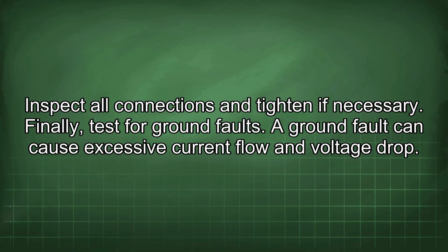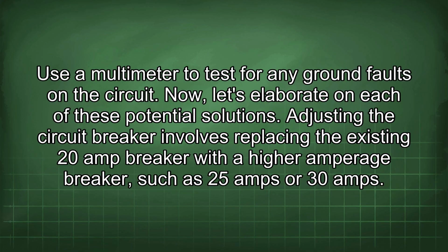Finally, test for ground faults. A ground fault can cause excessive current flow and voltage drop. Use a multimeter to test for any ground faults on the circuit. Now, let's elaborate on each of these potential solutions.